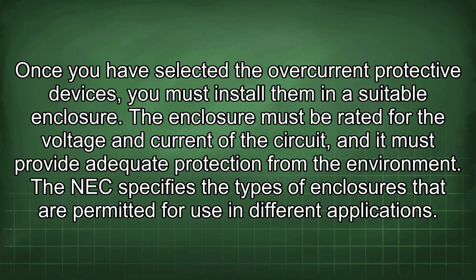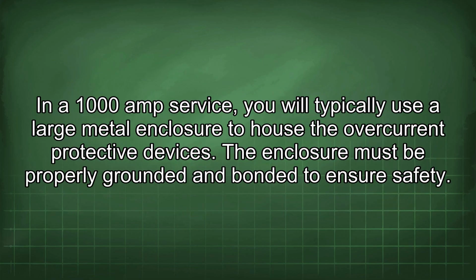Once you have selected the overcurrent protective devices, you must install them in a suitable enclosure. The enclosure must be rated for the voltage and current of the circuit, and it must provide adequate protection from the environment. The NEC specifies the types of enclosures that are permitted for use in different applications. In a 1000 amp service, you will typically use a large metal enclosure to house the overcurrent protective devices. The enclosure must be properly grounded and bonded to ensure safety.